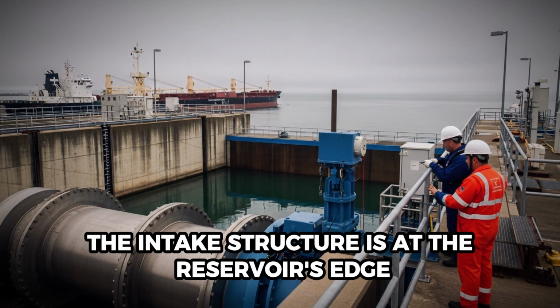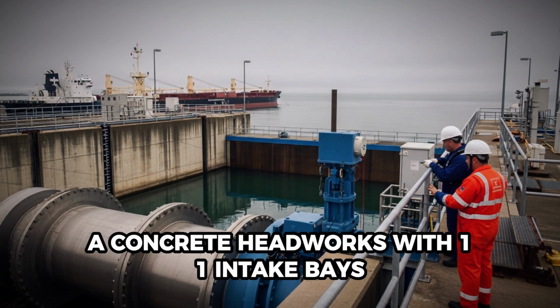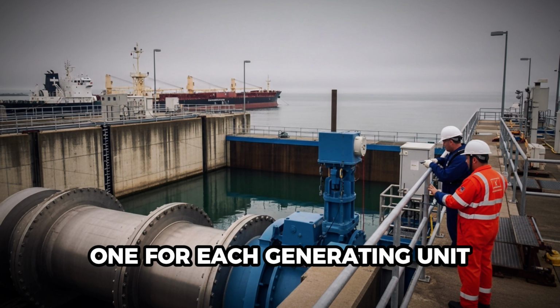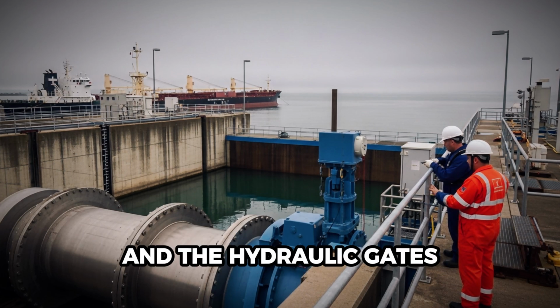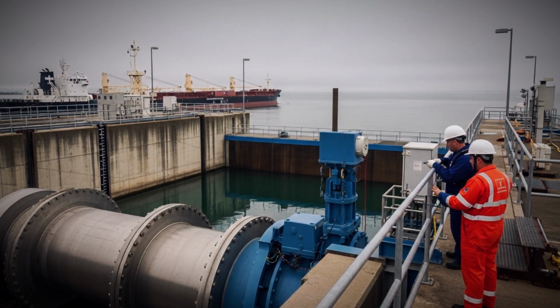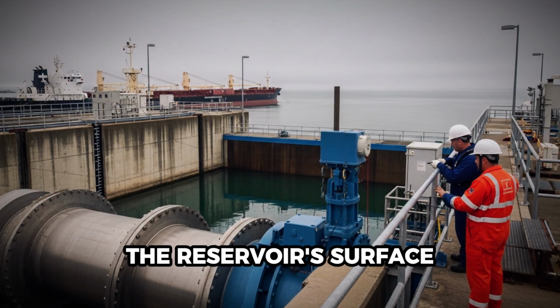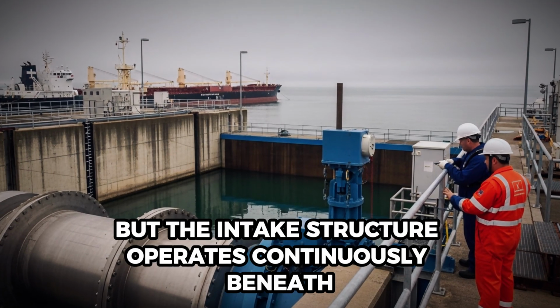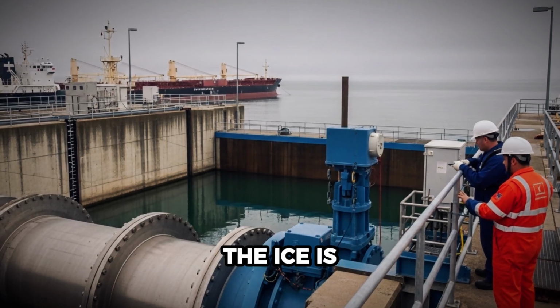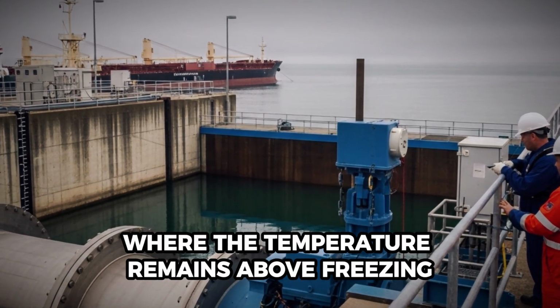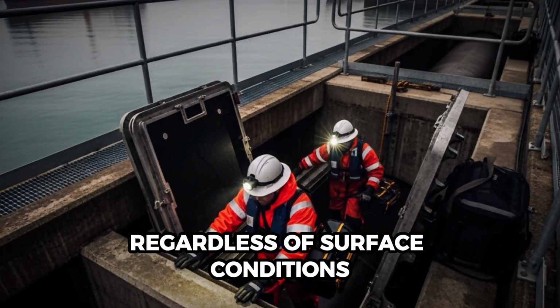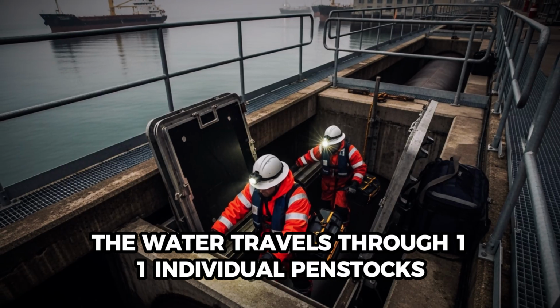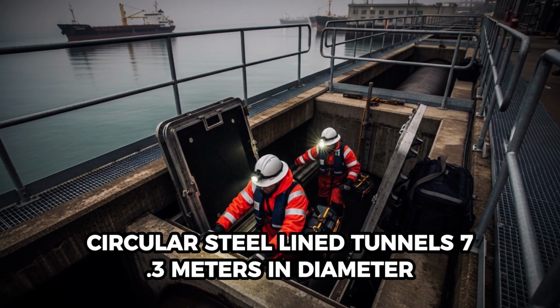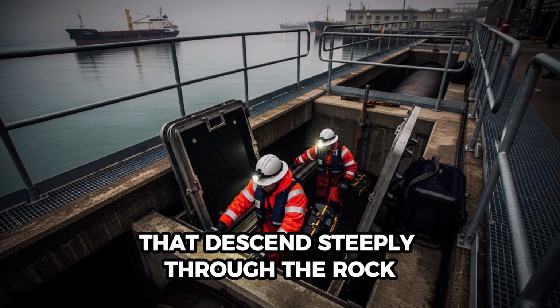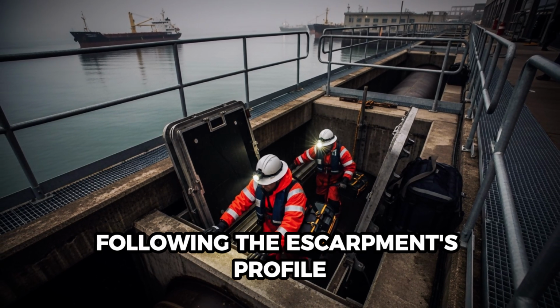The intake structure is at the reservoir's edge, a concrete headworks with 11 intake bays, one for each generating unit, fitted with trash racks and stop logs and the hydraulic gates that control flow into the tunnel system. The intakes are submerged. The reservoir's surface may be ice-covered for 6 months of the year, but the intake structure operates continuously beneath the ice, drawing water from a depth where the temperature remains above freezing regardless of surface conditions. From the intakes, the water travels through 11 individual penstocks, circular steel-lined tunnels, 7.3 meters in diameter, that descend steeply through the rock, following the escarpment's profile, until they reach the powerhouse cavern 300 meters below.